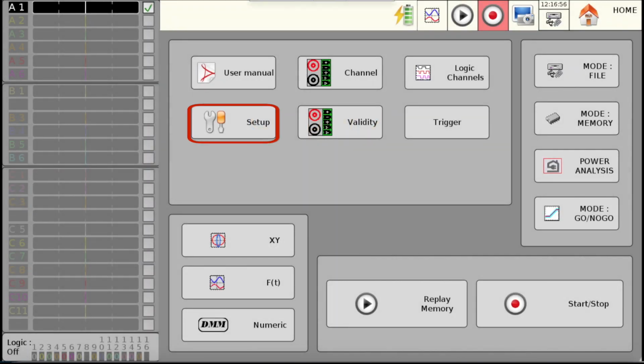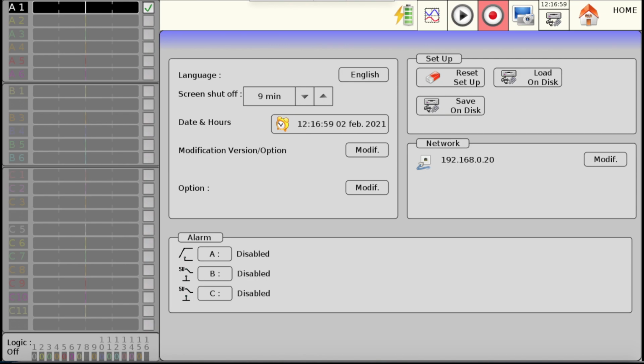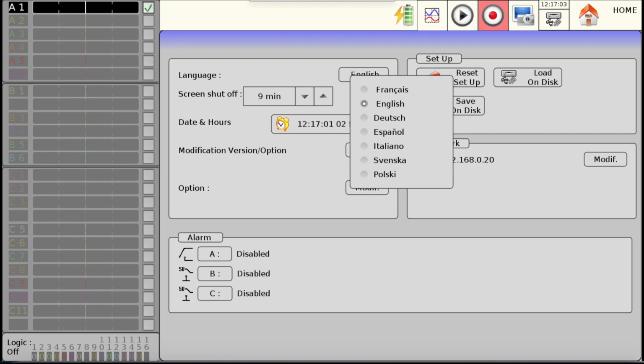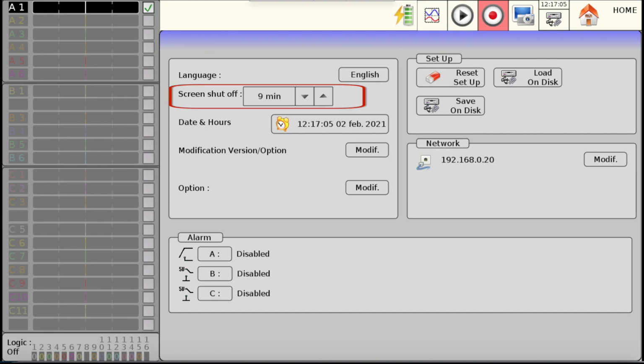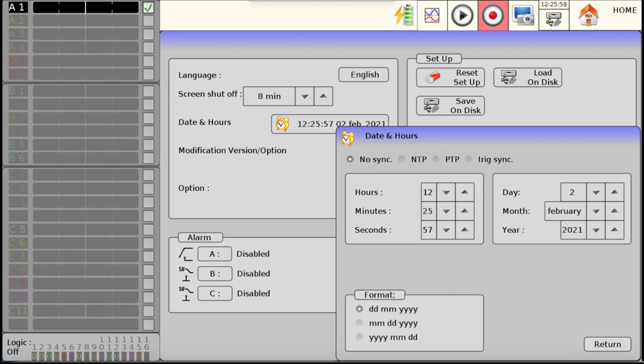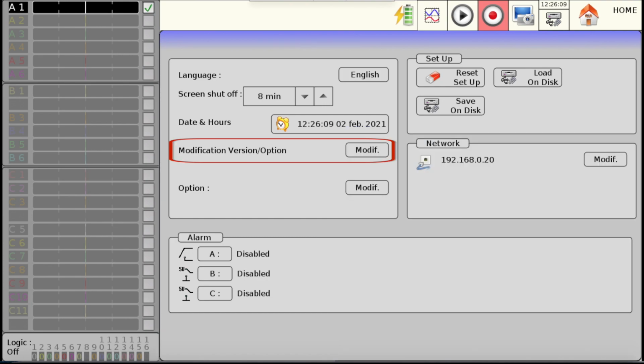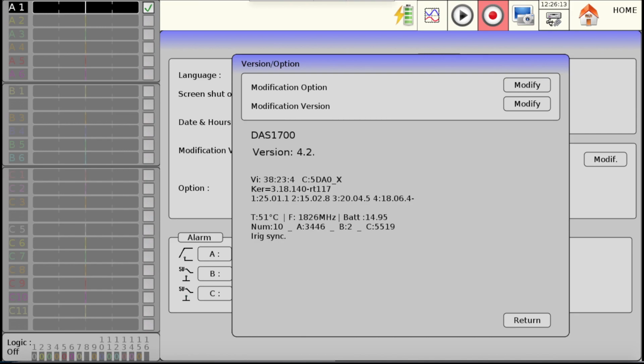Access the Setup menu to configure your DAS1700. Select the language of the instrument. Set the delay before the backlight is turned off. Set the date and hour of the instrument or access the timestamp setting via NTP or PTP server or via IRIG or GPS functions. Access the Modification Version Options menu to update your instruments or to add an internal software.